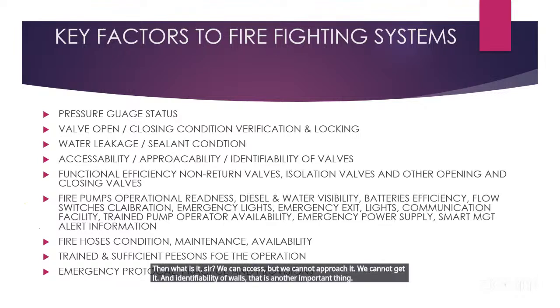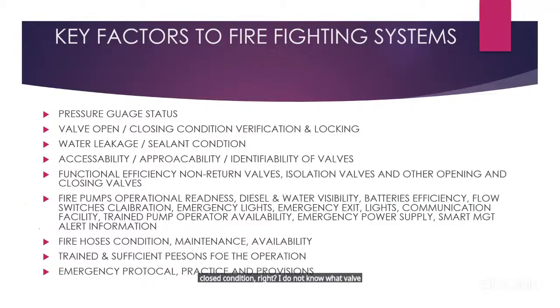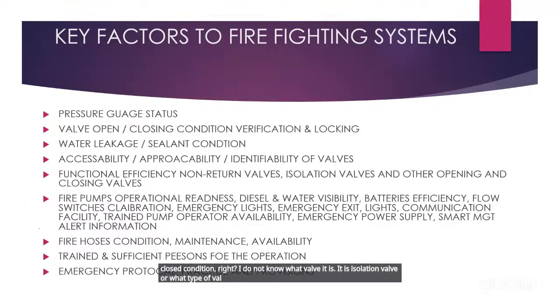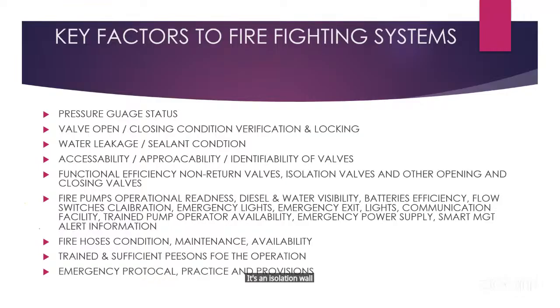The sprinkler valve may be there, but we cannot reach it. Even if you can access it, approach it and reach it, I do not know whether it should be in open or closed condition. I do not know what valve it is, whether it is an isolation valve or what type of valve. So there must be a marking on each valve. A plate with a number should be hanging there, saying it's an isolation valve. That marking should be there.